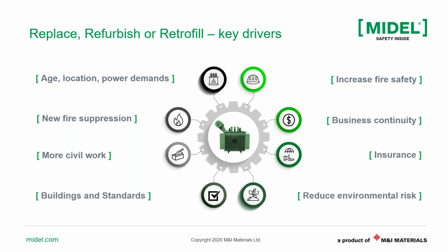Now, if we are in a situation like that, when you retrofill that transformer with an ester, you increase its fire safety. You may increase business continuity, so reducing the probability of failure and power cut. Also, by retrofilling, you can satisfy the insurer. Sometimes insurers ask that you use a less flammable liquid, a K-class fluid, in that transformer. And of course, finally, with retrofilling, you can reduce the environmental risk if you have a spillage in that location.